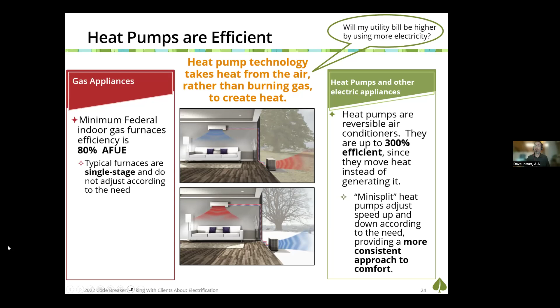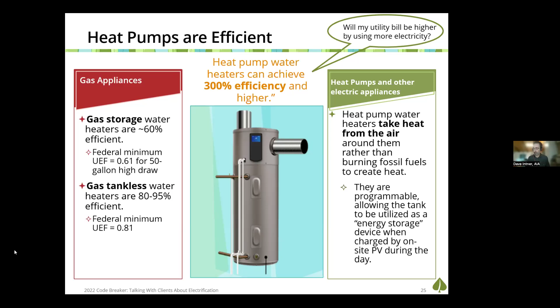So similar principle with heat pump water heaters, using that refrigerant loop to absorb heat from the ambient air around the heater, whether that's the interior space, the garage, or maybe it's in a small shed in a mild climate outside of the main house. But that process is going to be much more efficient than a storage or even a tankless water heater, which even the condensing types top out at about 95% efficiency. Yeah, same kind of principle. Again, even though you may think a unit of electricity costs more than a unit of gas, you're using so many fewer units that it comes out as a wash in terms of the overall cost of operation.